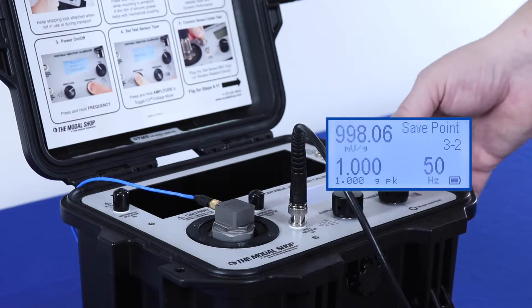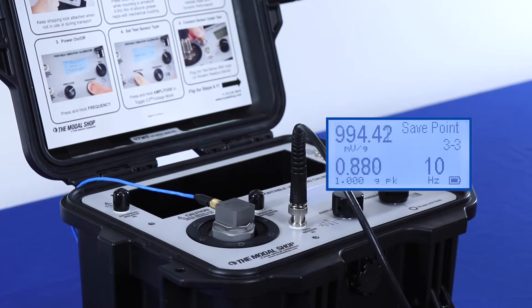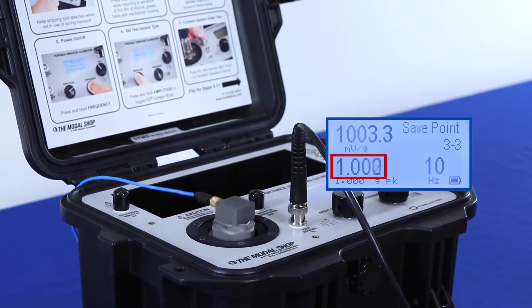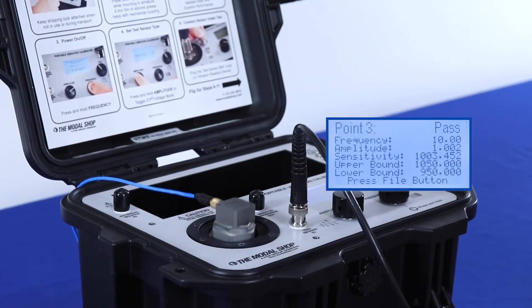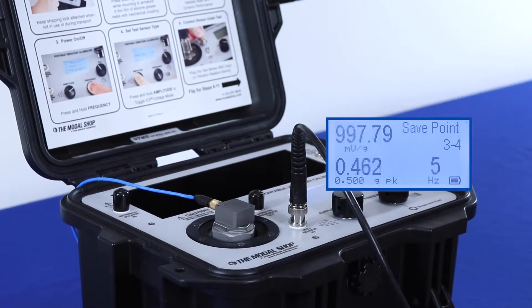Here at 50 Hz, I am once again going to pass calibration. Down to 10 Hz now at 1 G peak, which is a significant amount of displacement. We want to wait for the actual vibration amplitude to settle in and match the target, and once it does, we can press the file button to save that point.